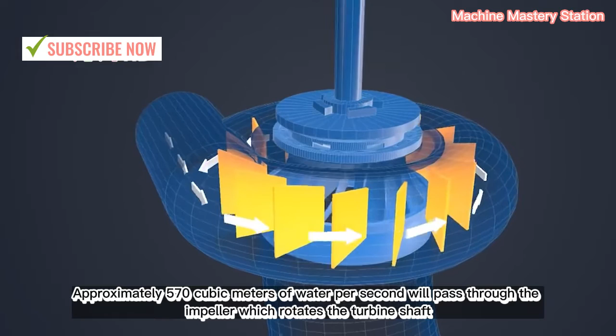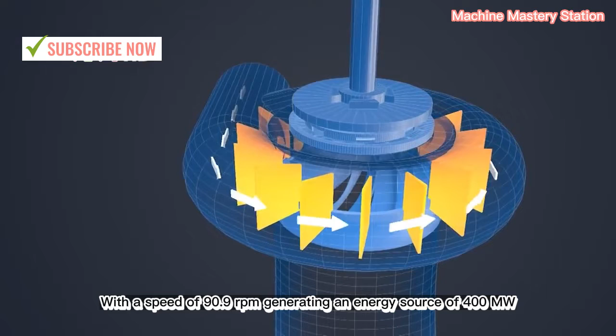This vein is the torsion chamber. Approximately 570 cubic meters of water per second pass through the impeller, rotating the turbine shaft at a speed of 90.9 revolutions per minute, generating an energy source of 400 megawatts. The generator terminal voltage is 18 kilovolts, raised to 500 kilovolts through a step-up transformer, and flows to the national grid.